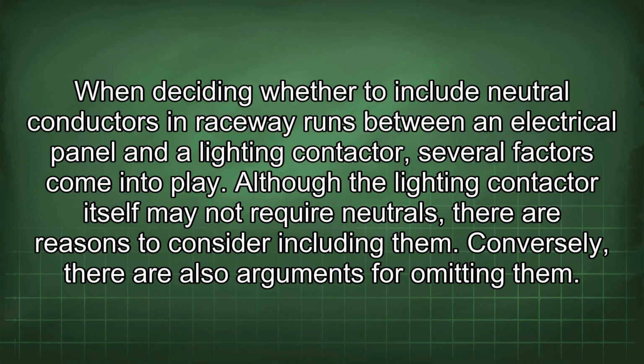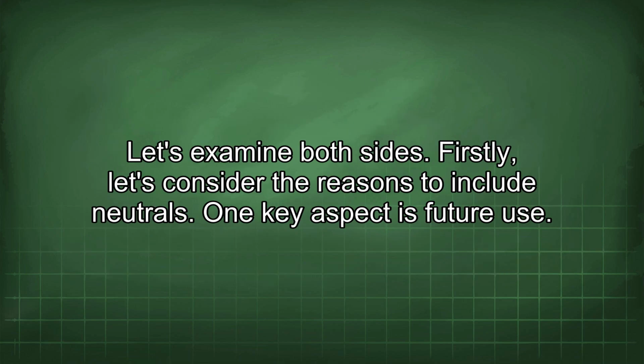When deciding whether to include neutral conductors in raceway runs between an electrical panel and a lighting contactor, several factors come into play. Although the lighting contactor itself may not require neutrals, there are reasons to consider including them. Conversely, there are also arguments for omitting them. Let's examine both sides. Firstly, let's consider the reasons to include neutrals.